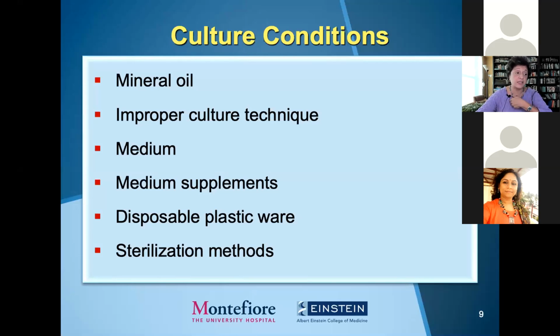Attention must also be paid to sterilization methods, as some can produce residual toxicants. For example, a catheter should not be sterilized with ethylene oxide, as this could have deleterious effects on the embryo. All items from manufacturers and clinics should be sterilized properly in order to avoid the introduction of contaminants. Proper procedures for autoclaves and dry sterilizers must be followed, including regular maintenance and monitoring of the effectiveness of these sterilizers using biological methods. Even the products of dead microorganisms, such as the lipopolysaccharide membrane of gram-negative bacteria, can result in the destruction of embryos. For this reason, most fluids and contact materials are tested for endotoxin, and they must pass strict quality control standards.